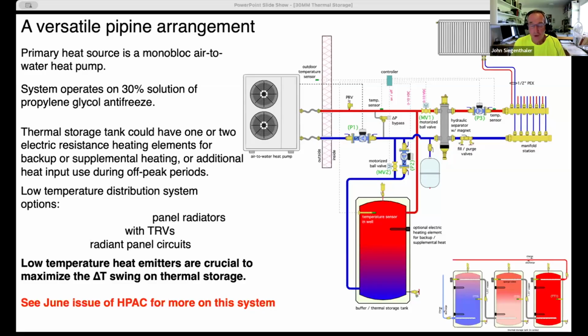And if you follow through the charging mode versus the discharging mode of that tank, both modes are going to help preserve the stratification. You also see that the pipes come in horizontally instead of vertically. And down in the lower right, it's a little hard to see at that scale, but one of the systems we've been working on, and we're going to get to that in just a minute, we're using what are called sparge tubes inside the tank. And these are basically internal headers that have holes drilled in them.